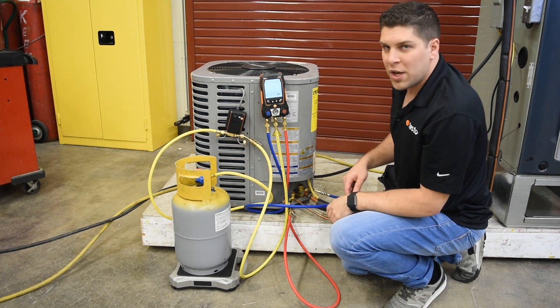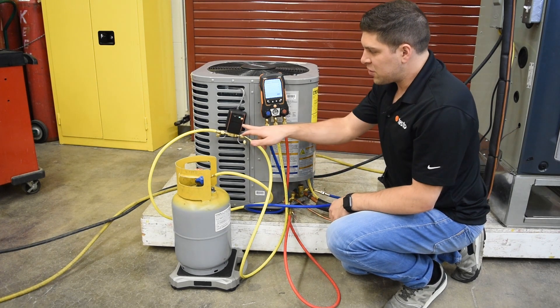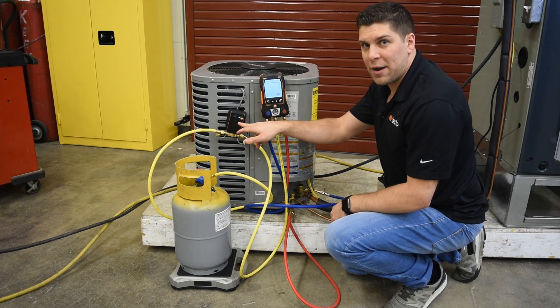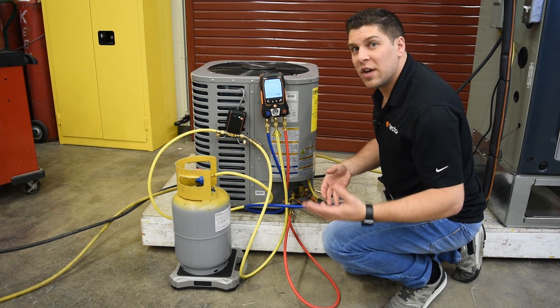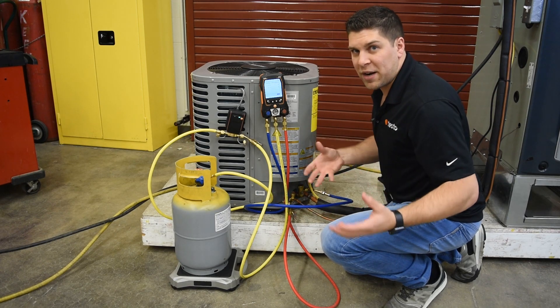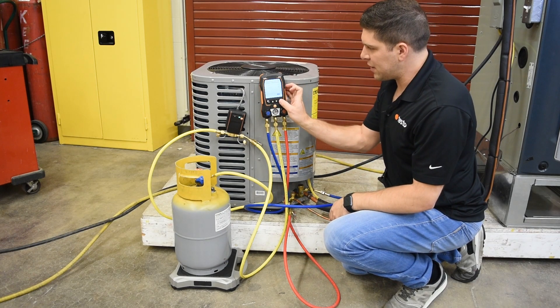When you turn on the valve, you'll hear it click once — that's just a test to make sure it opens and closes. Green means the valve is closed and red means it's open. The orange blinking works like your Testo smart probes, indicating that it's trying to pair. Everything pairs the same way as every other smart probe in your toolkit, and on the screen you can select everything.